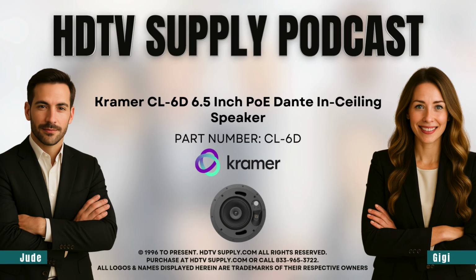First, you have PoE, or Power over Ethernet. Which is standard for things like VoIP phones or security cameras. But can a network switch really drive a loudspeaker? I mean, we're talking about physically moving air here. It absolutely can. The documentation shows this unit pulls up to 30 watts at peak directly from the network cable. That is enough to drive the 6.5-inch woofer and the tweeter to a really significant volume for background music or paging. Wow. So you effectively eliminated the need for a local power outlet. And the central amplifier rack, yeah, they're just gone.